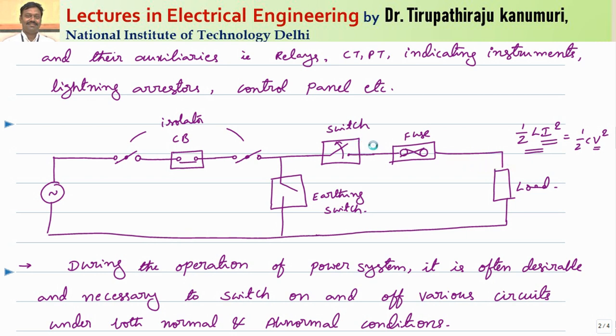In order to protect under fault conditions, the device used in our house is a fuse. The fuse is designed such that under normal operating conditions it operates normally without any heat. But whenever the current exceeds the rated capacity, we can decide how much fault current it should protect against. Whenever the current crosses that point, the I²R loss in the fuse element produces heat. Once the current crosses some limit, the heat produced will be sufficient to melt the fuse element, and that element will burn and protect your equipment. Under normal or low load conditions, the switch is used for opening or closing the circuit. Under fault conditions, it is protected by using the fuse.